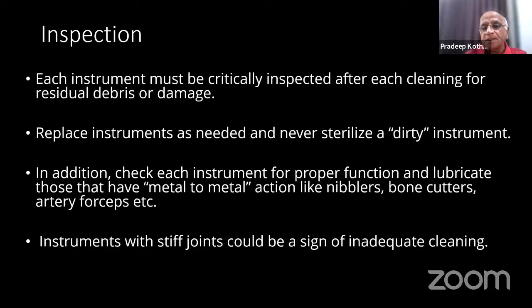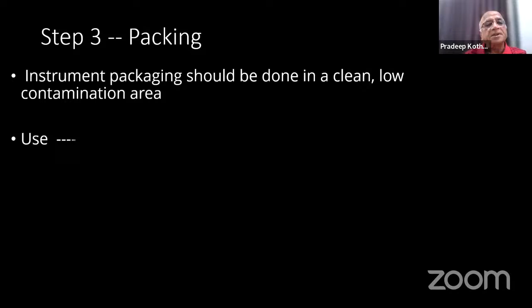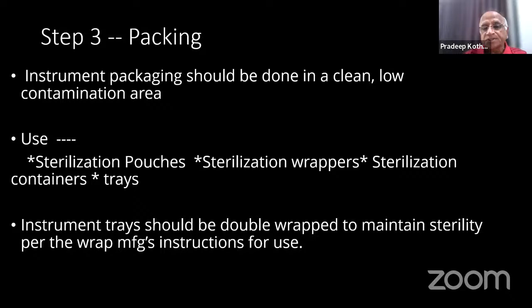After cleaning and inspecting, and once the instruments become dry, the instruments are packed in a clean, low-contamination area. Use sterilization pouches, sterilization wrappers, sterilization containers, or trays. Nowadays, people use a lot of trays. Instrument trays should be double wrapped to maintain sterility, as per the wrap manufacturer's instructions for use.